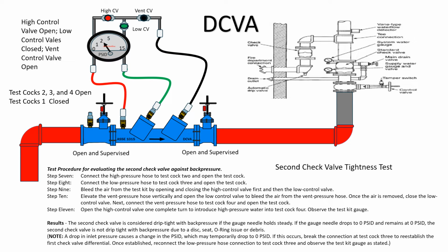Next, connect the vent pressure hose to test cock 4, and open the test cock. Step 11. Open the high control valve one complete turn to introduce high-pressure water into test cock 4. Observe the test kit gauge. Results. The second check valve is considered drip tight with back pressure if the gauge needle holds steady. If the gauge needle drops to 0 psid and remains at 0 psid, the second check valve is not drip tight with back pressure, due to a disc, seat, o-ring issue or debris.